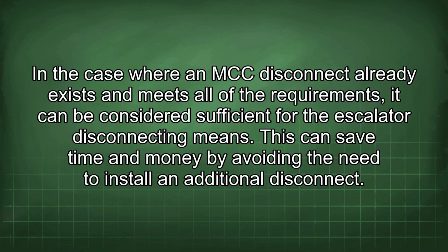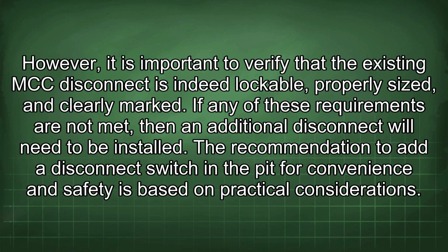In the case where an MCC disconnect already exists and meets all of the requirements, it can be considered sufficient for the escalator disconnecting means. This can save time and money by avoiding the need to install an additional disconnect. However, it is important to verify that the existing MCC disconnect is indeed lockable, properly sized, and clearly marked. If any of these requirements are not met, then an additional disconnect will need to be installed.